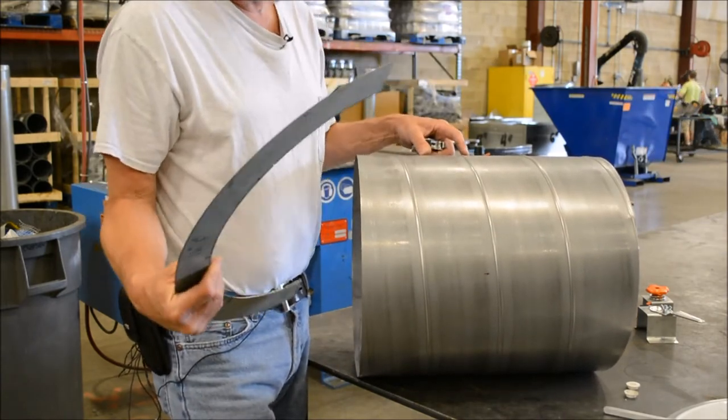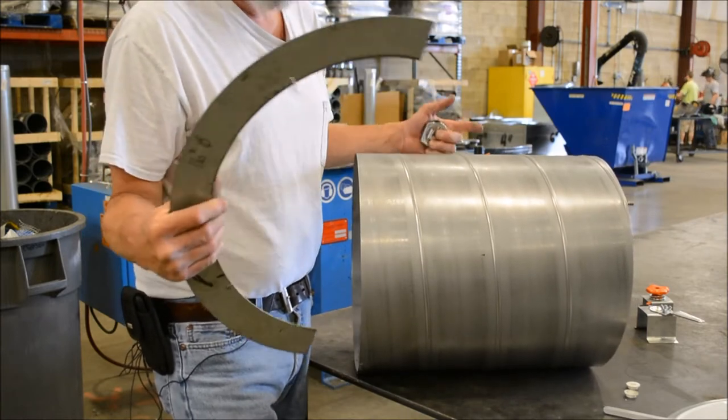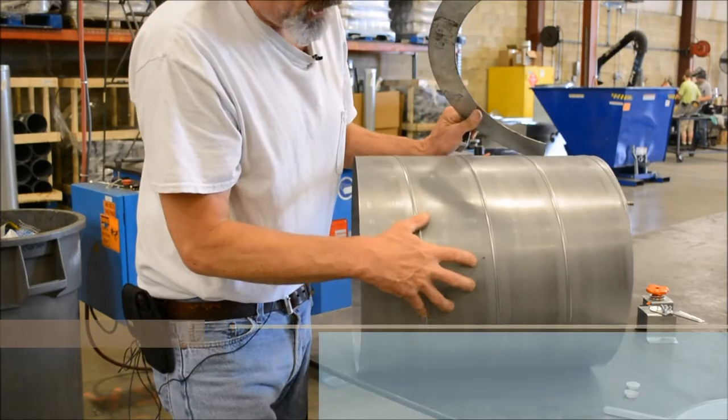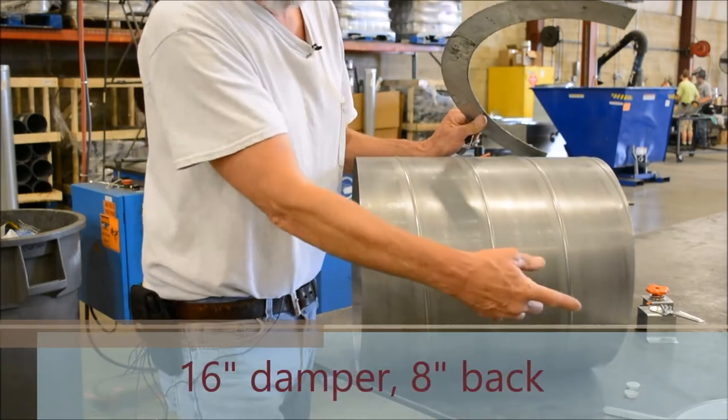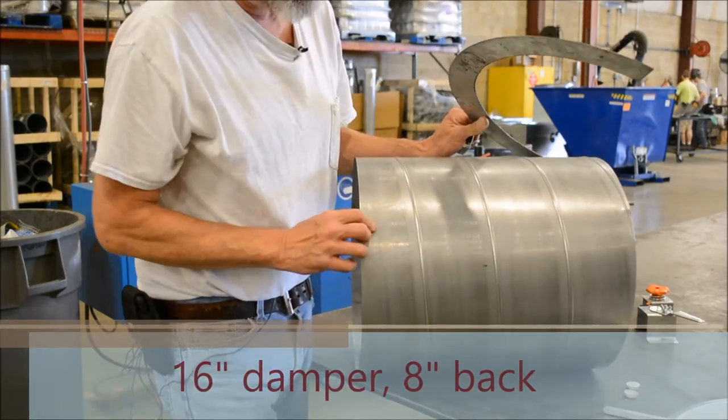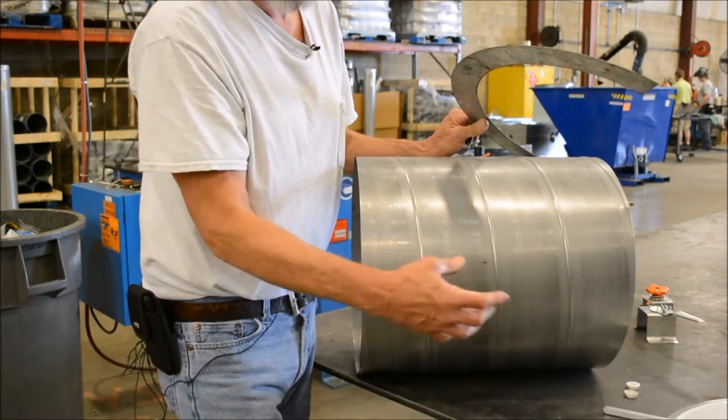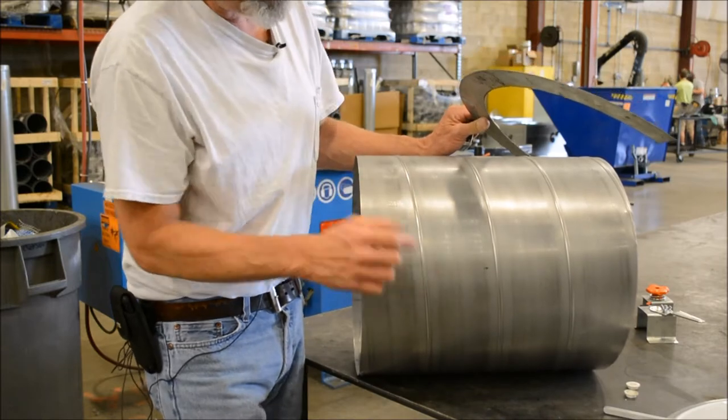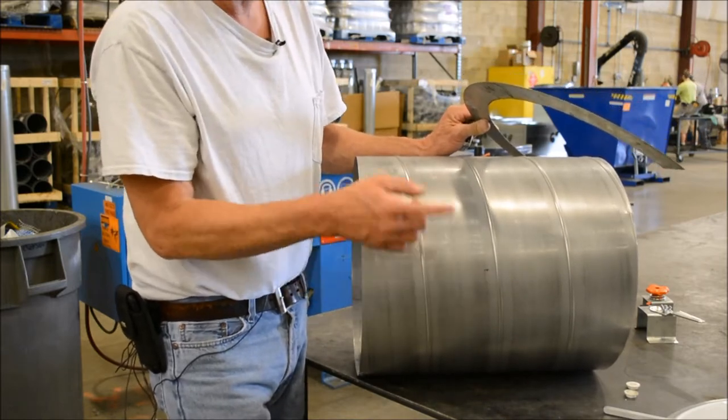piece that we use for installing dampers, gives us a quick mark. I come eight inches back because we got a 16 inch damper, we want to keep that halfway back so that way the blade's not out here in the opening. So what I'm gonna do is mark my pipe, then I'm gonna drill my five-eighth hole.